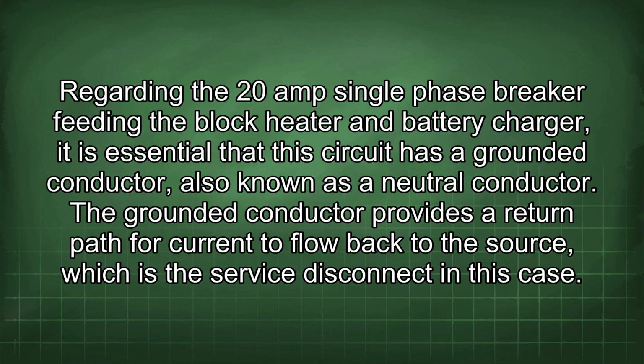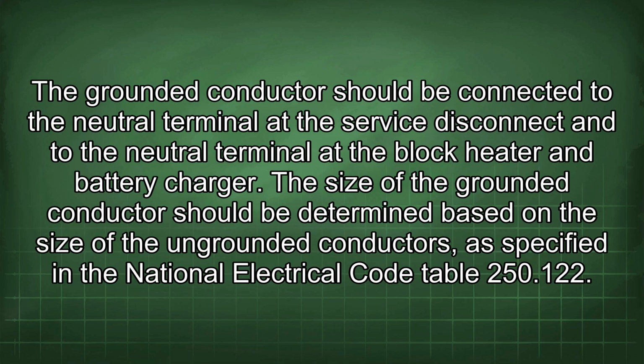Regarding the 20-amp single-phase breaker feeding the block heater and battery charger, it is essential that the circuit has a grounded conductor, also known as a neutral conductor. The grounded conductor provides a return path for current to flow back to the source, which is the service disconnect in this case. The grounded conductor should be connected to the neutral terminal at the service disconnect and to the neutral terminal at the block heater and battery charger.